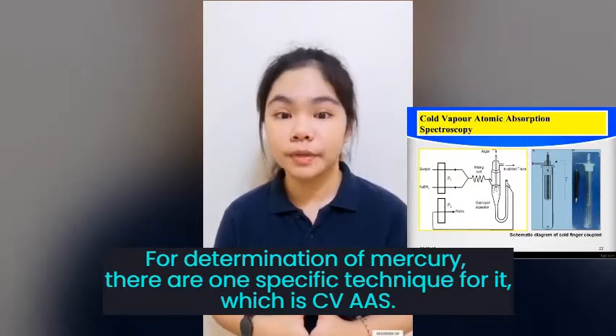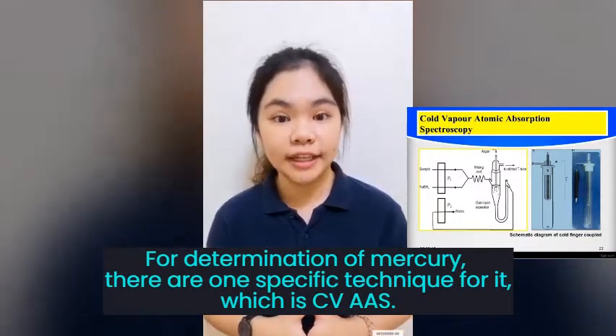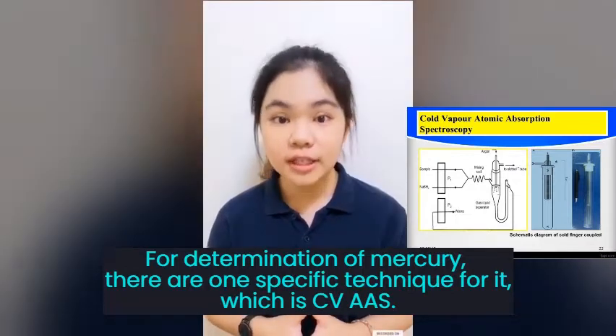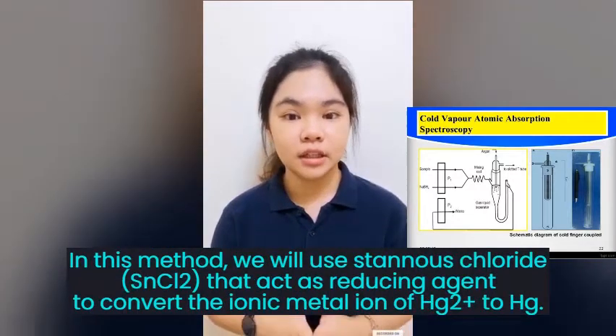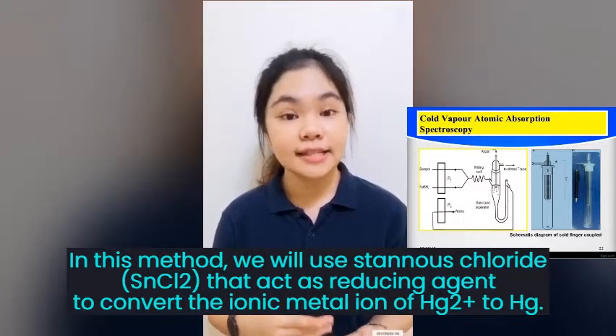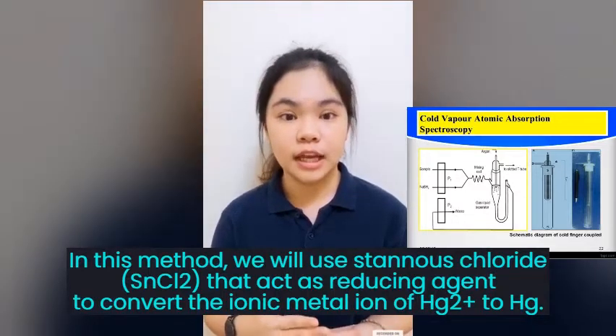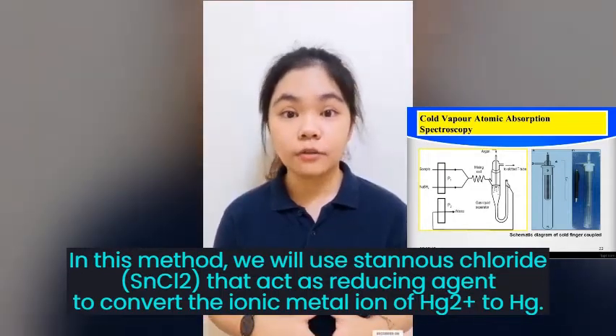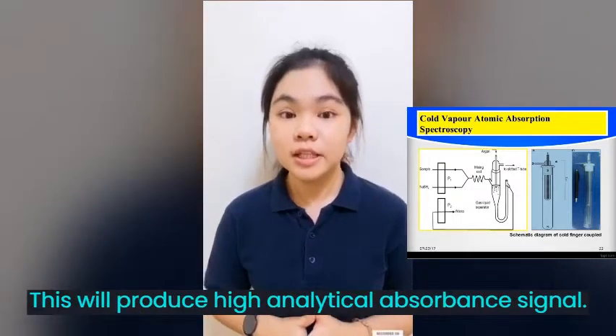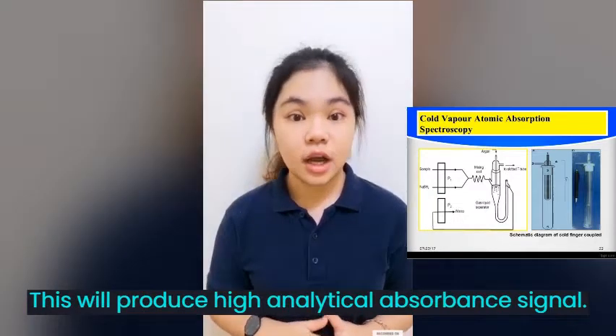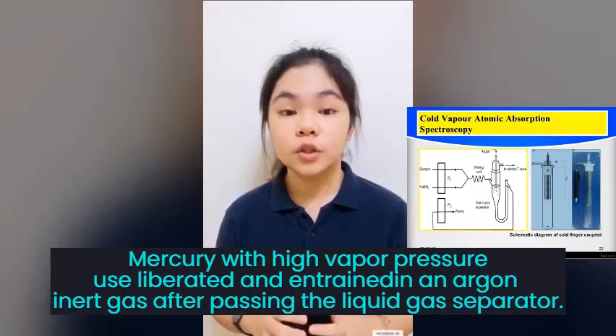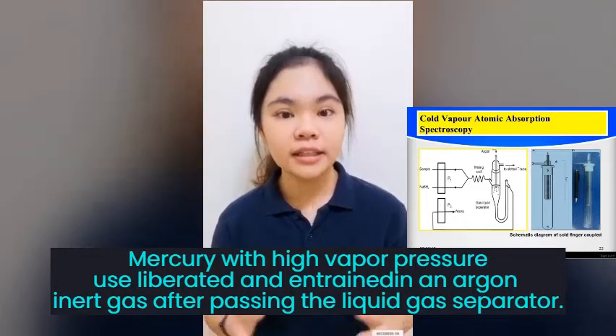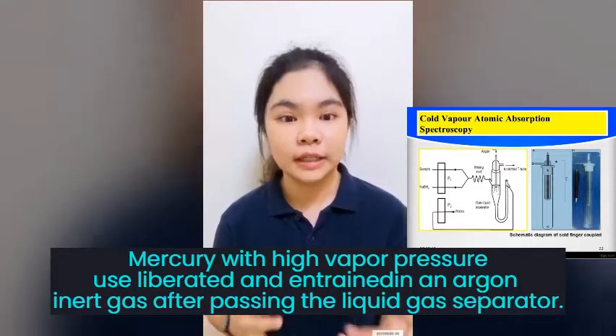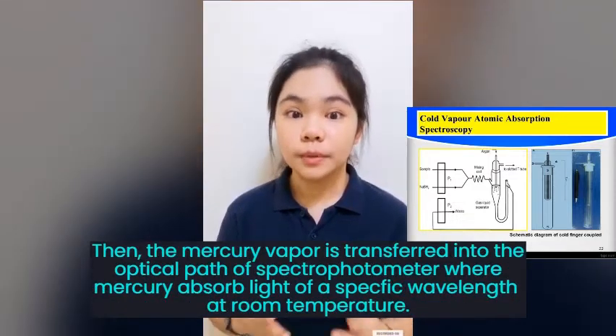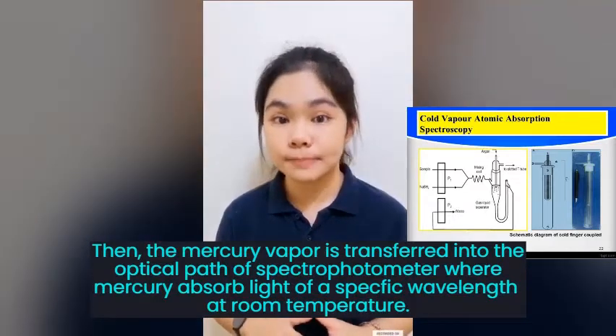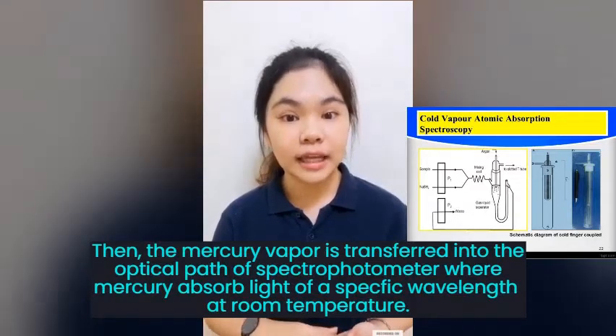For determination of mercury, there is one specific technique, which is cold vapor atomic absorption spectroscopy. In this method, we use stannous chloride, SnCl2, as a reducing agent to convert the ionic mercury Hg2+ to Hg. This will produce a higher analytical absorbance signal. Mercury with high vapor pressure is liberated and entrained in an argon inert gas after passing through the liquid gas separator.